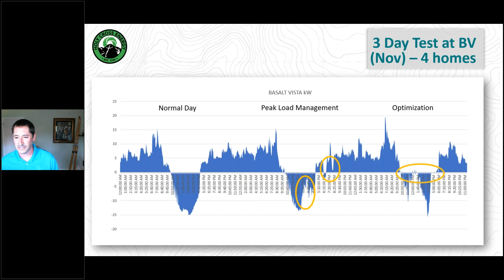This is a direct hive approach, just charging the batteries and setting the forecast to discharge between that time, with a call out into the system saying give me as much power as you possibly can, with no set value. On the third day we ran optimization, setting the transformer at 0. We still allowed the PV to generate into the grid since these are net metered, but the 4 houses together never went above 0 consuming during that time, running into the night, almost to 6:30 in the evening. Here are some overlays showing what it looks like when you move energy around, which is exactly what we're doing.